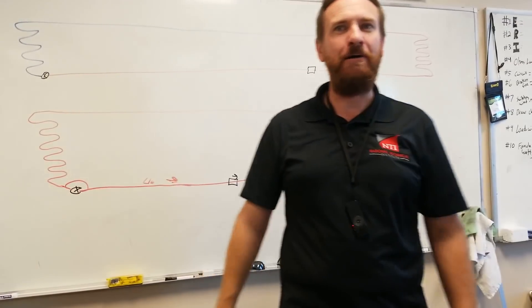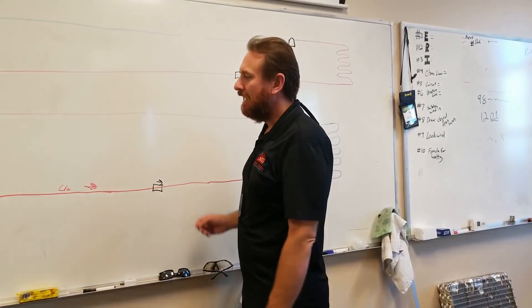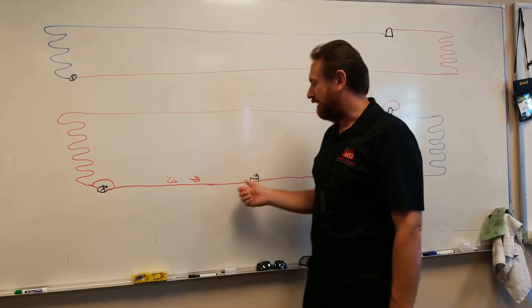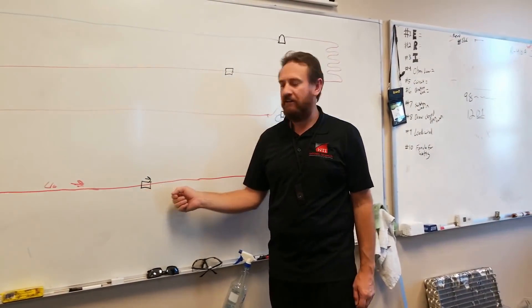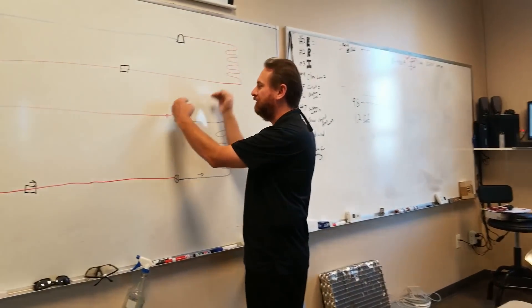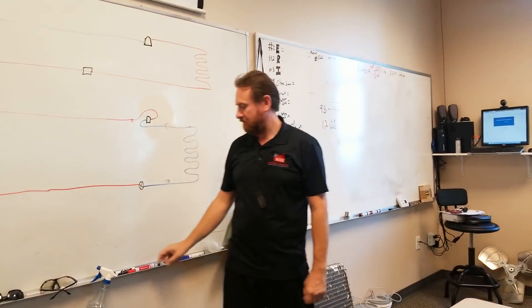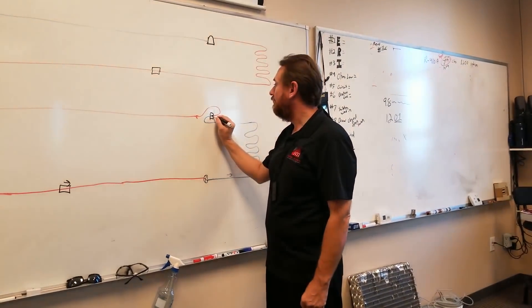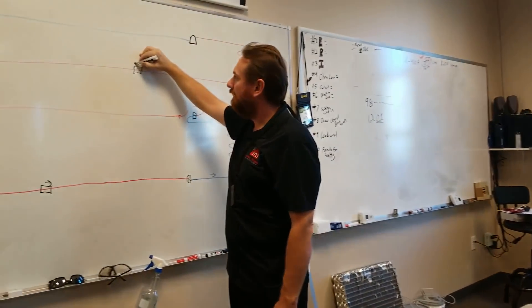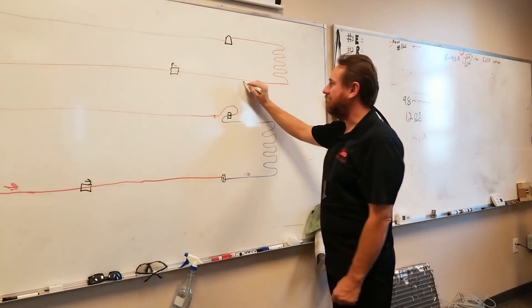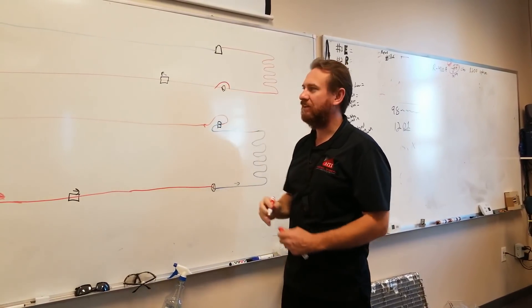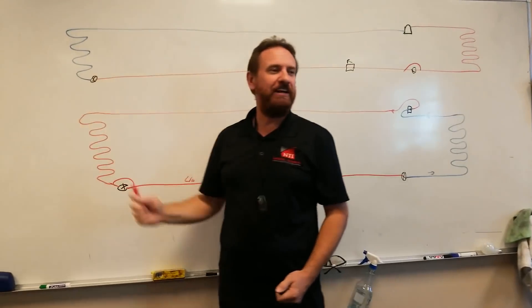All I have to do for a heat pump is in the fall — go outside or go to the inside unit and put a bypass around that metering device. Then I have to cut my filter dryer out and turn it around. I have to add a new filter dryer to the outside unit. And I have to cut the pipes from the compressor and swap them, because the compressor only pumps one way. Then in the summertime, we go and cut those pipes and put them back the other way, turn the filter dryer around, bypass or cut out the outside metering device, and reinstall the metering device inside.